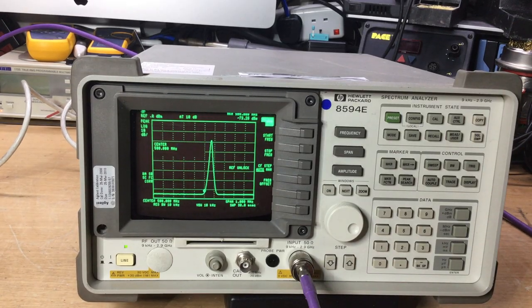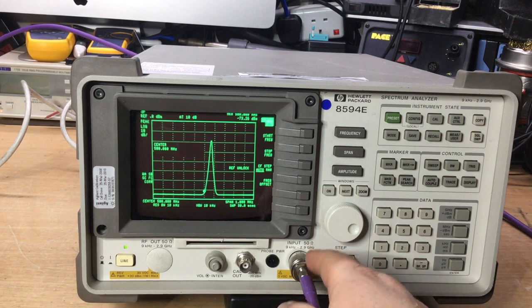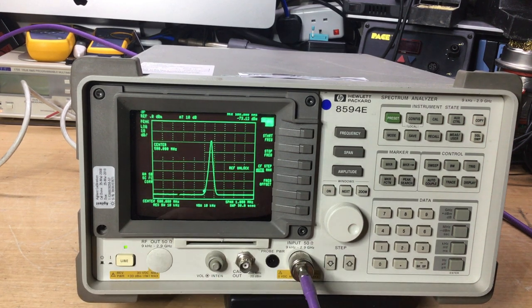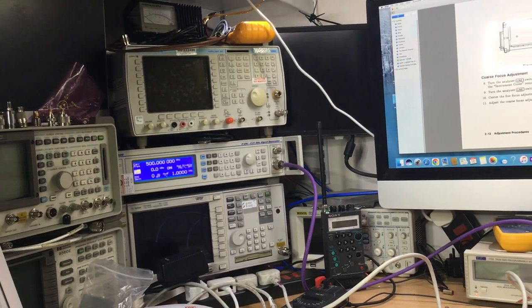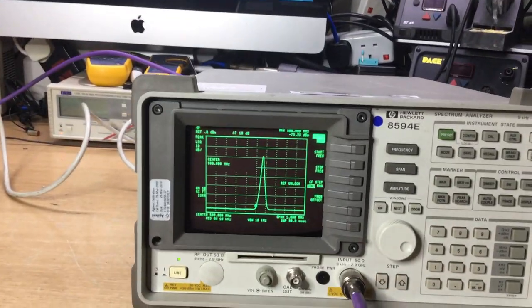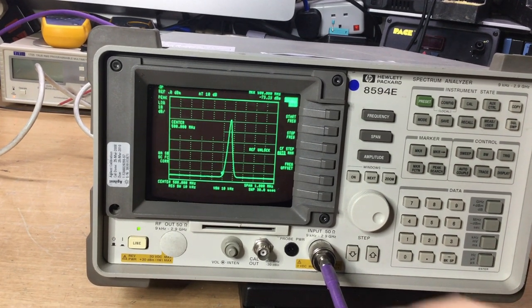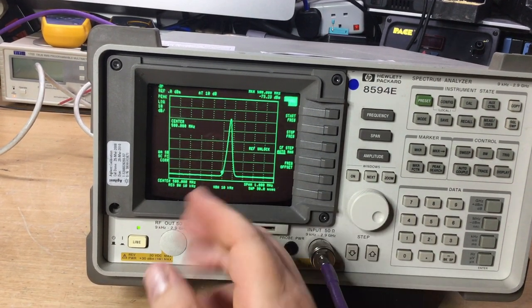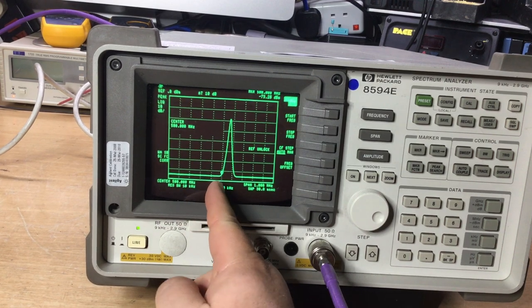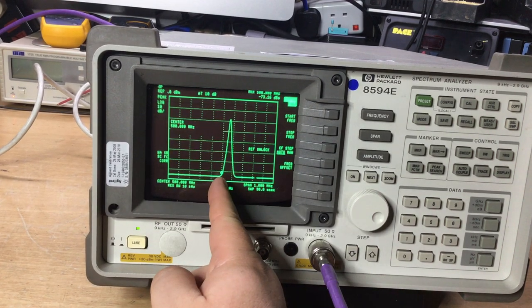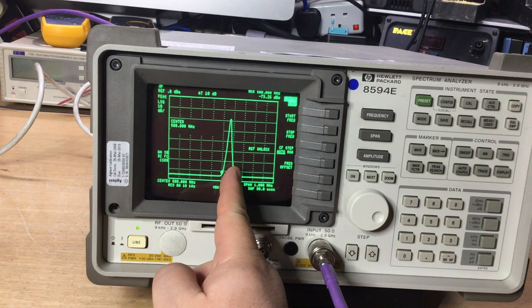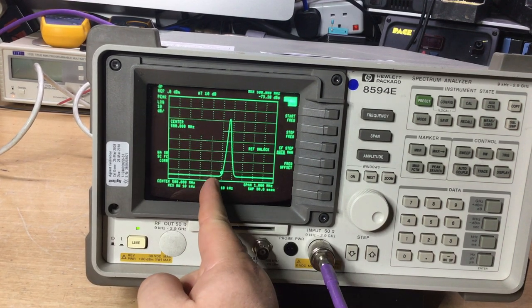Okay, so what we're doing now is I'm feeding a signal in on the type N socket on the front of the instrument. We're using the IFR signal generator, which is here, to generate a signal at 500 megahertz at 0 dBm. That, in accordance with that measurement, should now show us 500 megahertz frequency, which it clearly isn't, because 500 megahertz is the dead center dotted line, and the waveform is showing to the right, which means it's measuring a higher frequency than 500 megahertz.